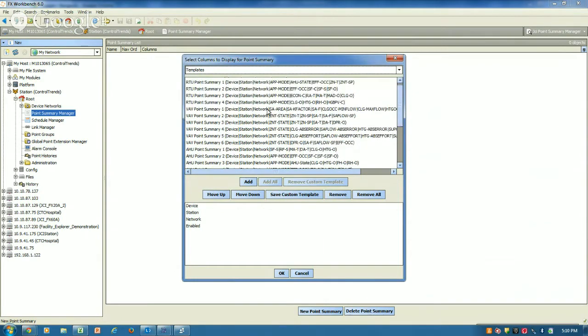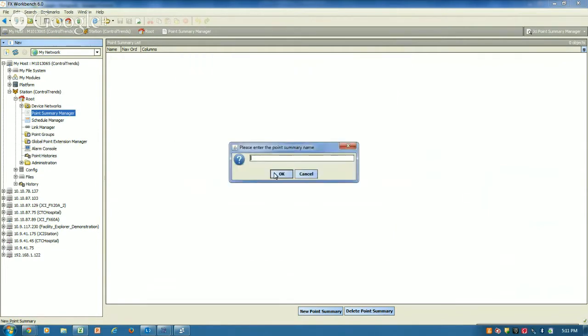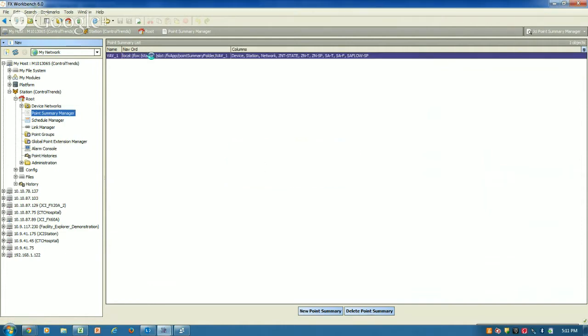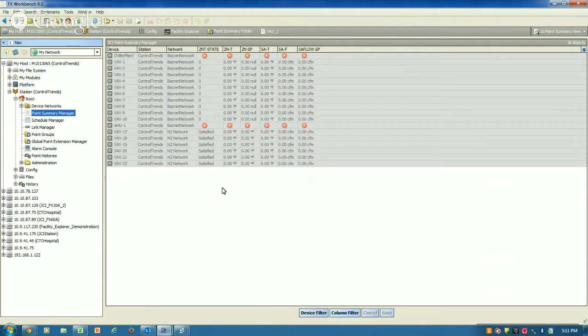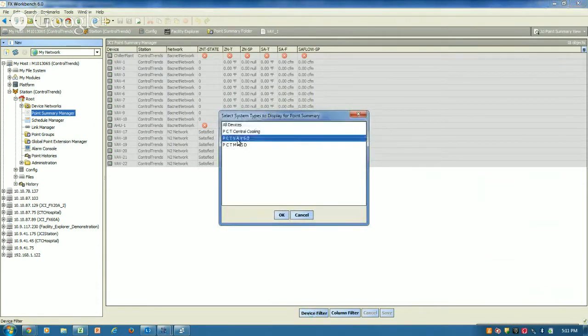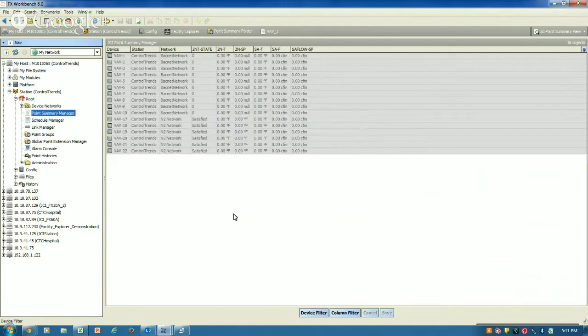Let's say we have VAV boxes here, and I want something that shows what state my controller is in, what the set point is, the supply air temperature, the flow, and the flow set point. I add that onto those points, hit OK, give it a name, and now every time I click on that, it goes through all my devices and shows what I have, filtered out to just the VAV boxes. Hit OK.